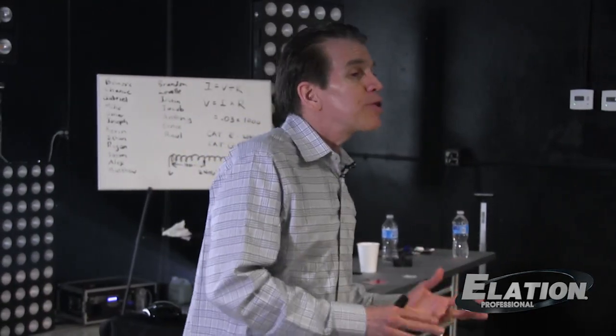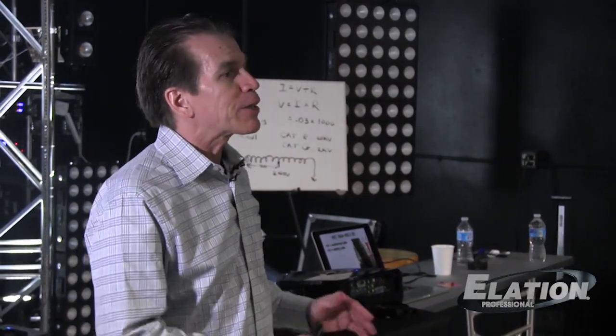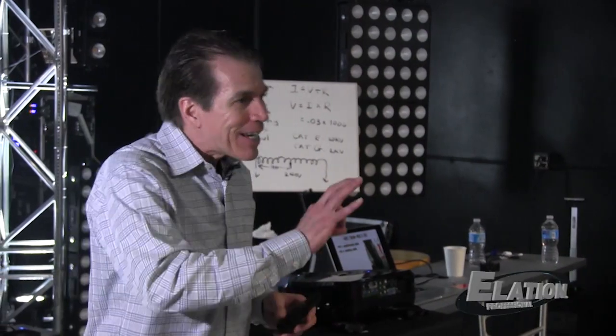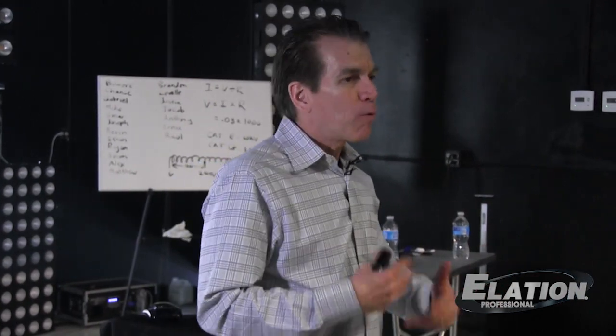So the city of LA could either shut down the broadcast of the Olympics or they could allow the use of welding cable. So what they said is, well, you can use it until after the Olympics are over, but after that, no more welding cable. So that's when type SC was developed. That's what we use now. Type SC is what's called extra hard usage cable. That means the jacket can withstand abrasions and cuts. If you lay it on the ground, you can walk on it, and it won't easily break. So that's what we use.